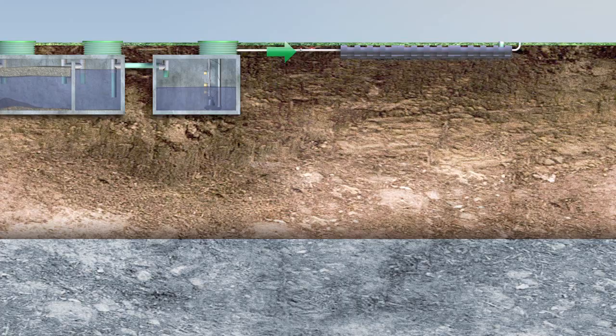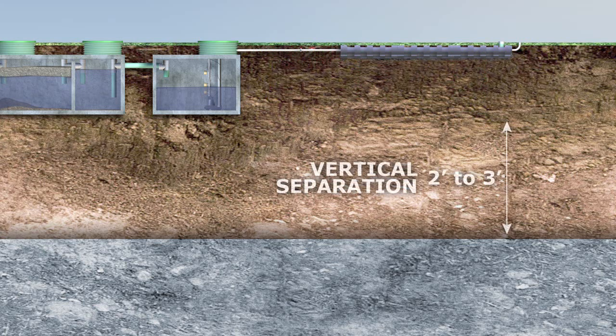Pressurized systems may be used where sufficient soil is present but the wastewater needs to be pumped to a certain area of the property. Pressure systems are also used when the soil type requires a specific dosing, or when vertical separation is 2 to 3 feet. In Washington State, pressurized systems need at least 2 feet of vertical separation — 12 inches less than conventional — because of how a pressurized system distributes the wastewater.